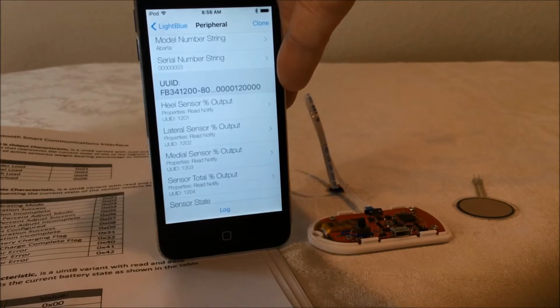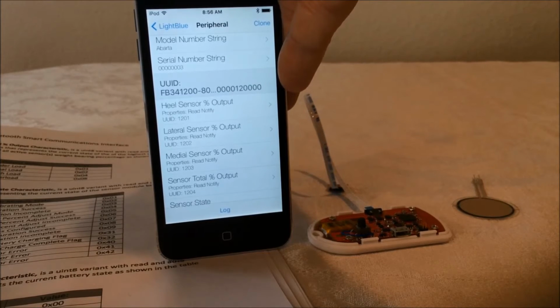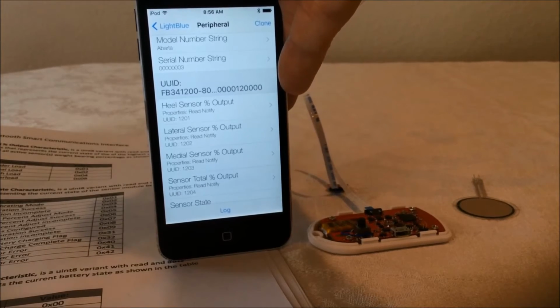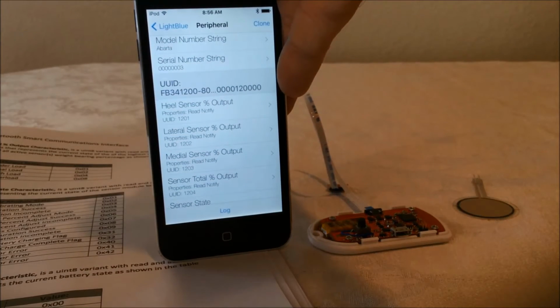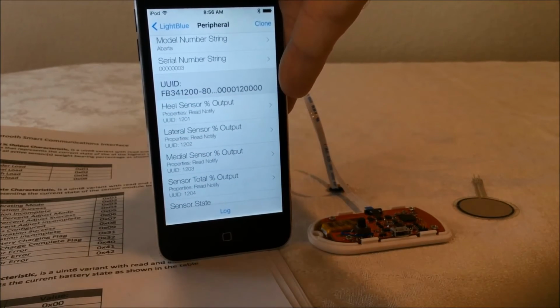So the device actually captures a value based on your weight on a good foot. During the calibration process it captures this value, but it's not interpreted or presented as a real-world weight — it's a static reference value obtained for comparison with the actual runtime weight.